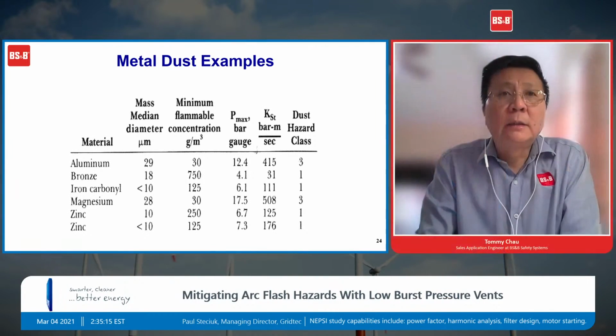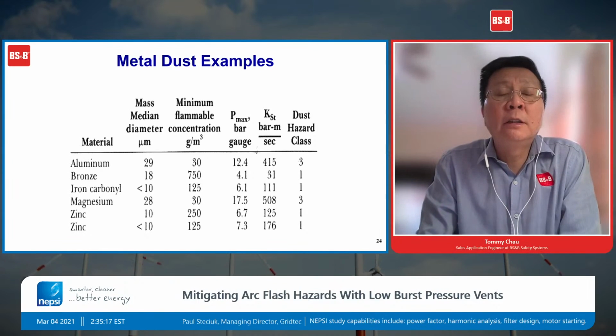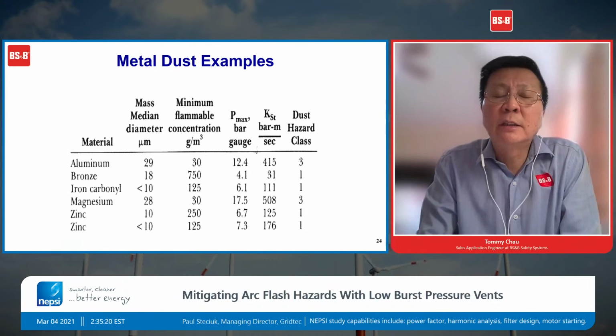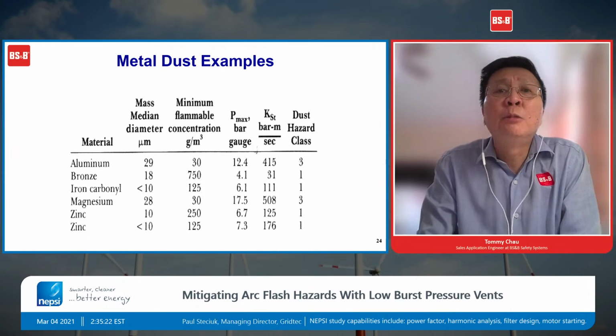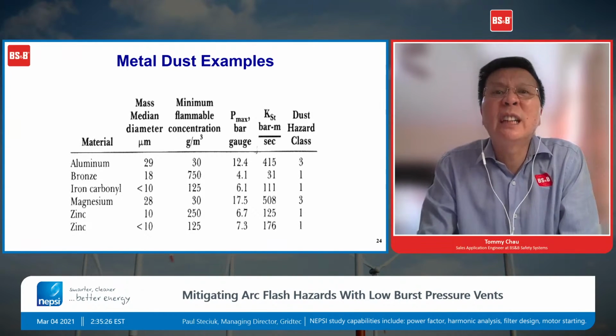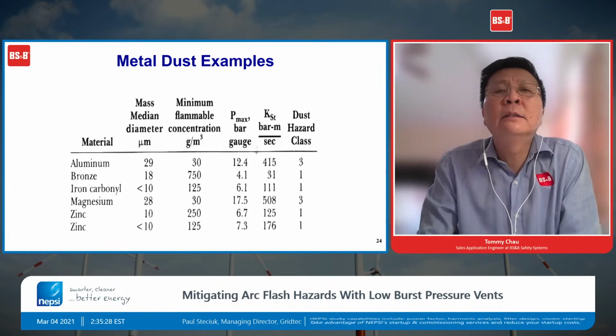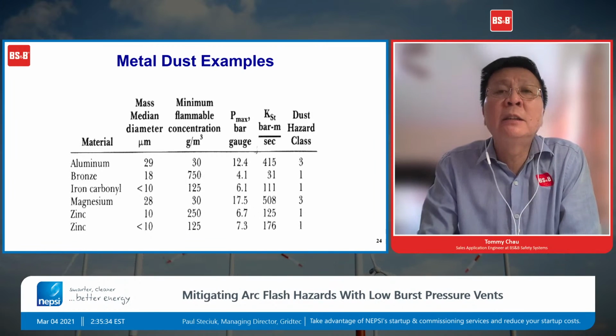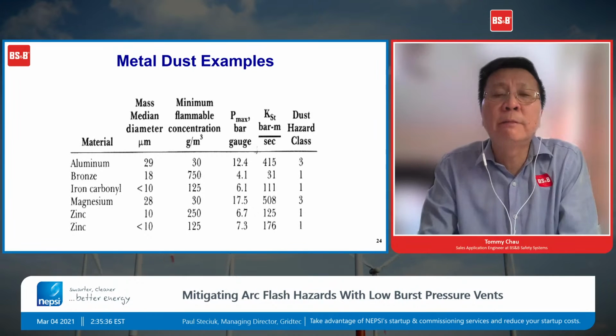Okay, so the KST value for different metal dusts, as you can see, is very high. Aluminum has a KST value of 415, so obviously this is a class 3 dust explosion. Magnesium is over 500 on the KST value. So metal dust is very, very explosive.